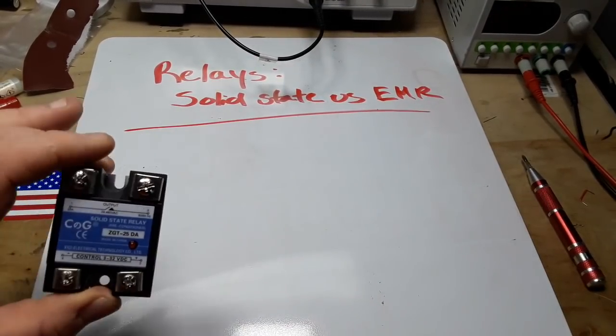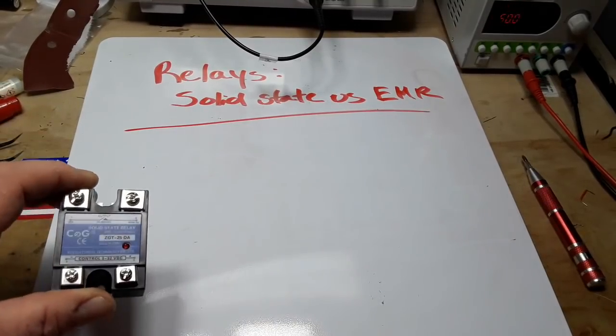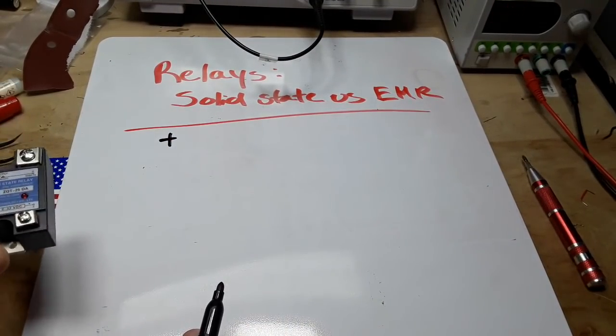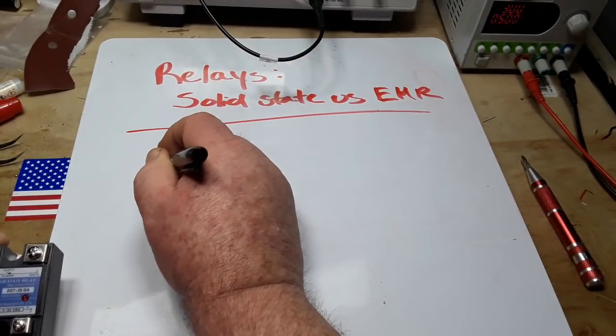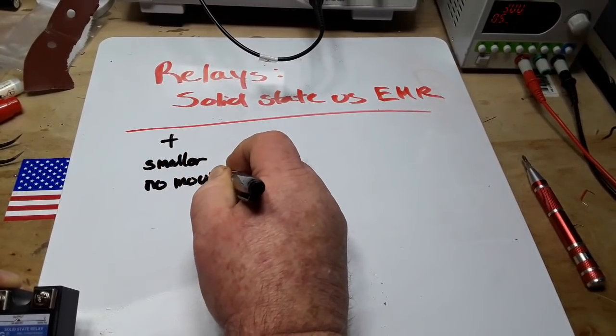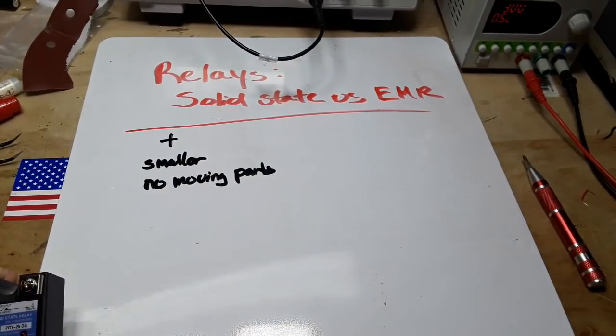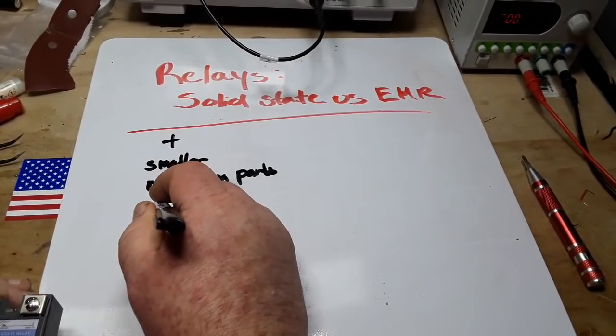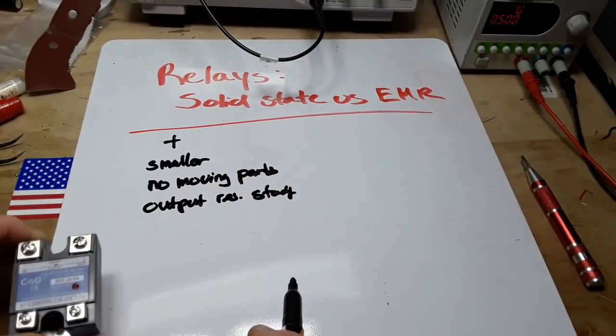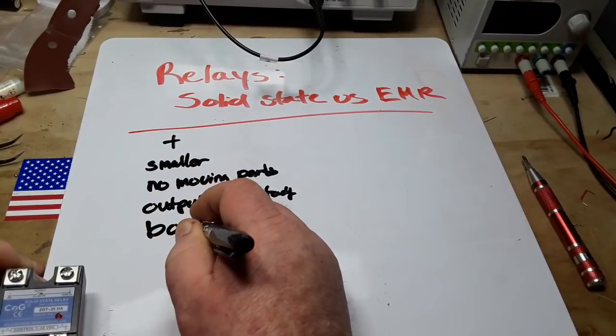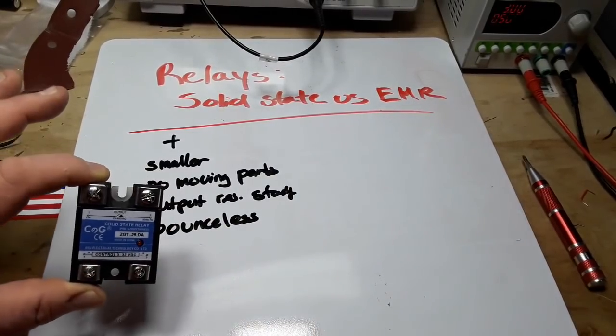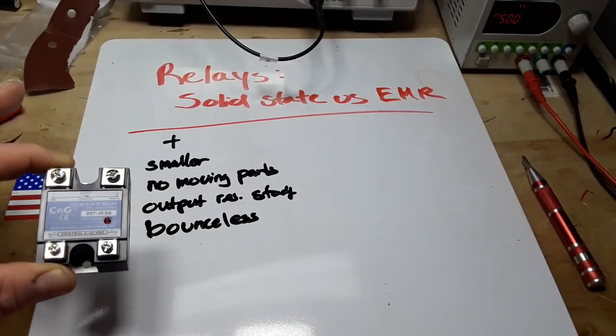So what are some advantages and disadvantages of the solid state relay over the electromechanical relay? Well, on the plus side, the solid state relay, the SSR is generally smaller. It has no moving parts, so it lasts longer. Its output resistance is steady regardless of the load, and they are bounceless. There's no springy bar making contact that can bounce. It's solid state. There's nothing that can go bad there.